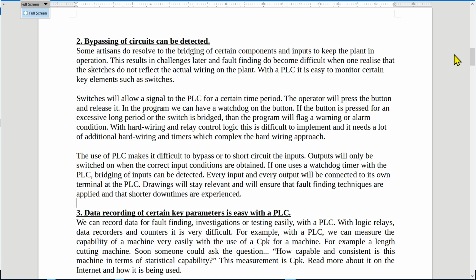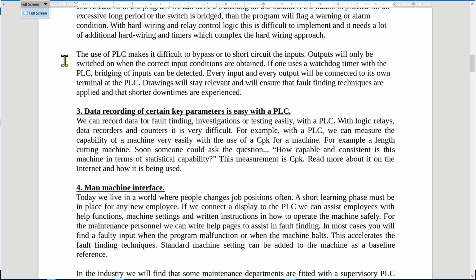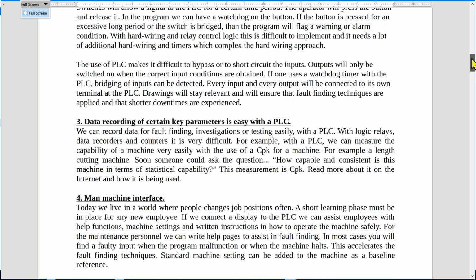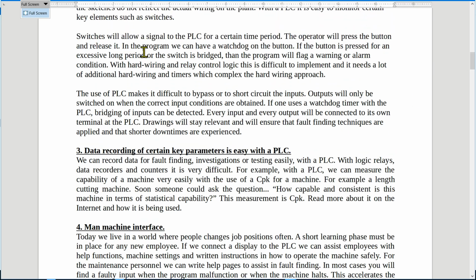We can also make use of a normal input with a timer. If the input is on for a certain time, then the timer will time out and make an alarm. Now, the use of a PLC makes it difficult to bypass or to short circuit the inputs. Outputs will only be switched on when the correct input conditions are obtained safely. If one uses a watchdog timer, for example, with the PLC, bridging of inputs can be detected.